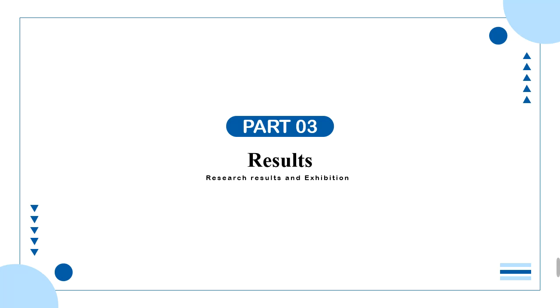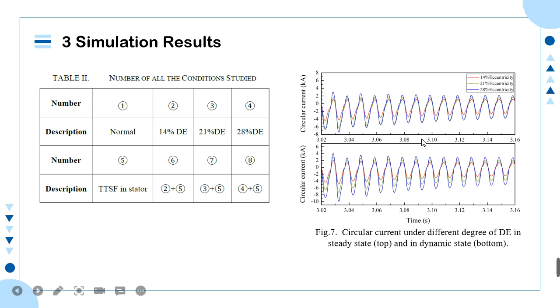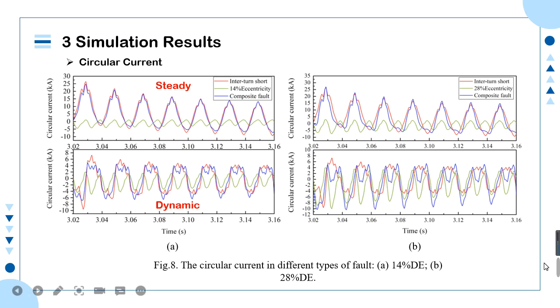Part 3. Results. In order to simplify the description, we numbered the 8 conditions studied as is displayed in Table 2. The circular current waveforms under different degree of eccentricity are shown in Figure 7. With the degree of eccentricity increasing, the amplitude of circular current also boosts. As is depicted in Figure 8, the circular currents under composite fault are not equivalent to the sum of the other 2 cases.